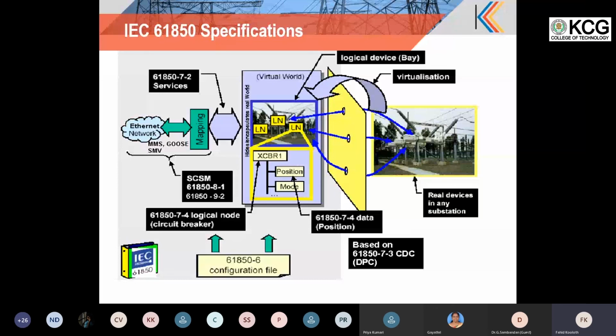So these defined logical nodes are there. I can exchange this. I will get a correct response if it is successful. If it is a failure, I will get another response. All these details are defined in 7-2. But it does not define the actual payload to achieve this function. That is defined by 8-1 or 9-2, which is called the specific communication service mapping. Specific communication service mapping onto MMS, GOOSE, sampled value, which is taking 7-2 and loading it over the protocol payload, the existing Ethernet TCP/IP mechanism, transferring the data out. So that is defined under 8-1 and 9-2.